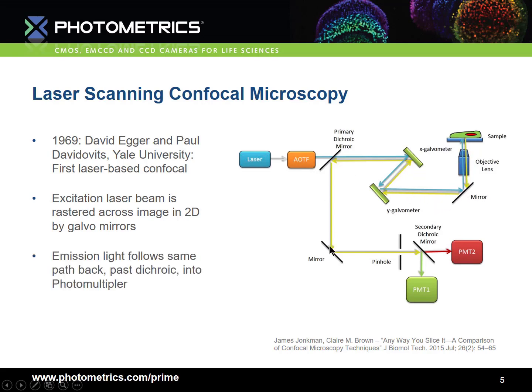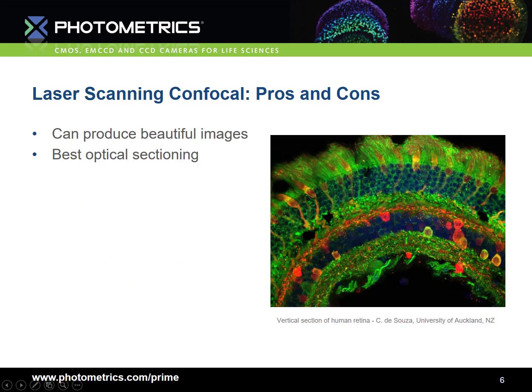The first microscope using this principle was the laser scanning confocal microscope, invented in 1969 by David Egger and Paul Davidovits at Yale University. As only light from a single point of focus within the sample can pass through any given pinhole, we therefore need to scan this point across our sample to generate an entire 2D image. This is achieved through X and Y galvo scanning mirrors. The excitation laser beam is raster scanned across the image by these mirrors. The returning light passes through the optical system before being focused through a pinhole and reaching some photomultiplier tubes. The images resulting from this technique can be truly beautiful — very good contrast, very good optical sectioning in multiple colours.